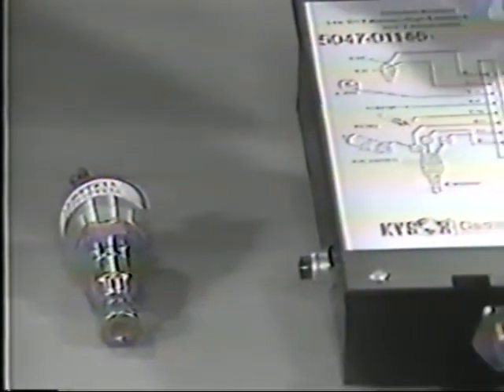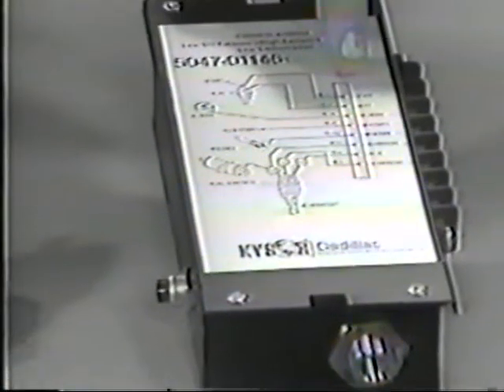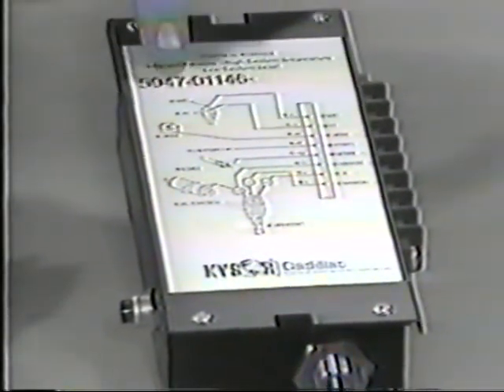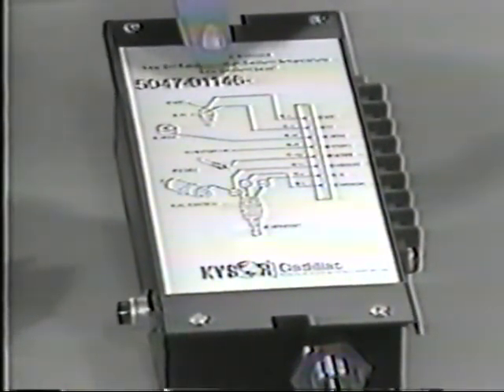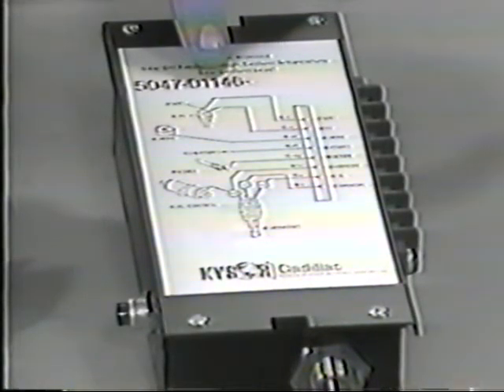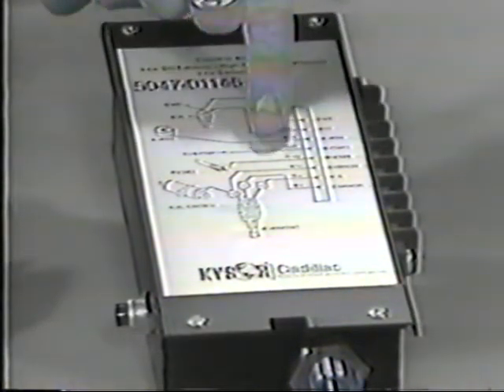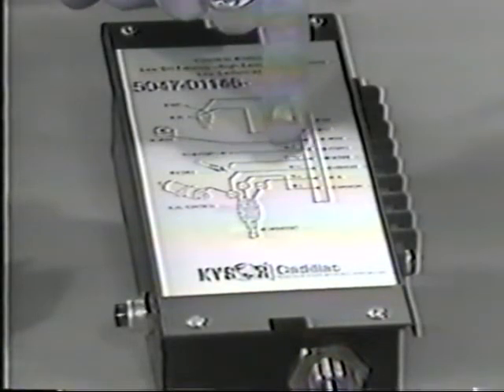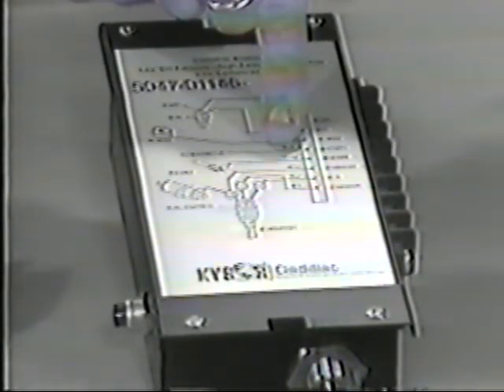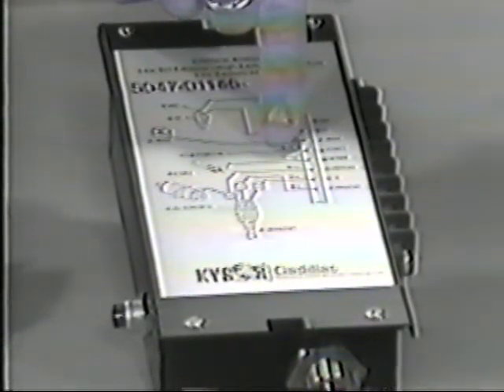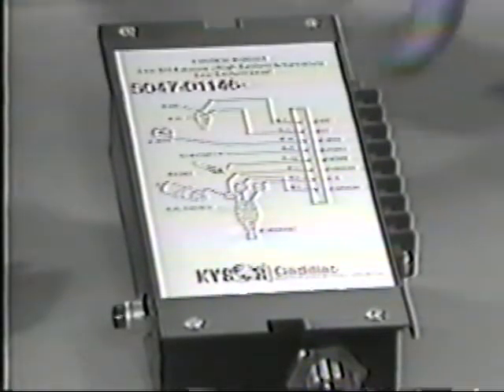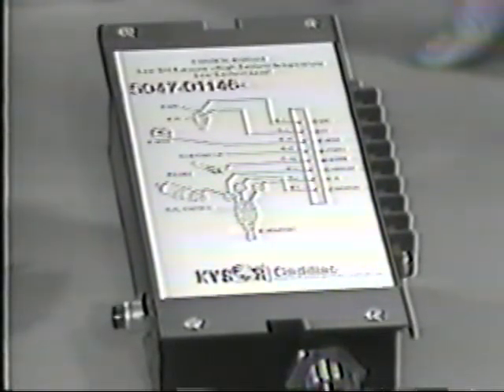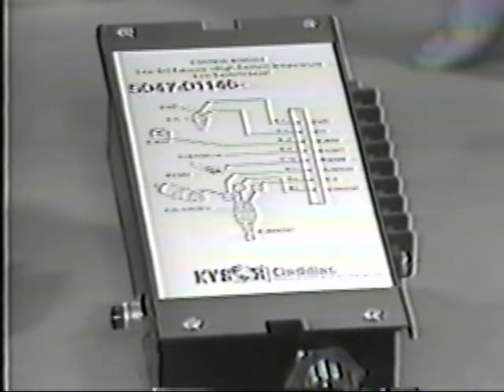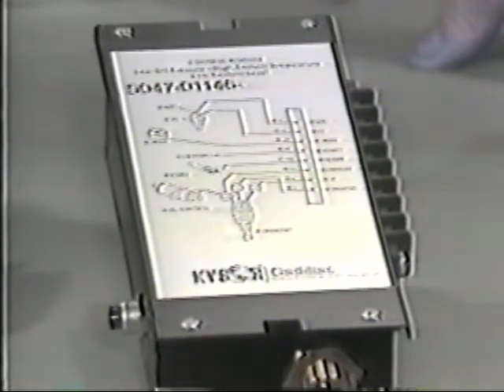Finally, there is a system diagram on the face of the module. This, along with the part number, helps in determining whether you have a two-way or three-way system. A three-way system has this orange low coolant level wire shown on the diagram. On a two-way system, this will not be shown, and there is a blank spot on the connector at that point. Before we get into system operation, let's talk about the differences between 9038, 41, and 42.